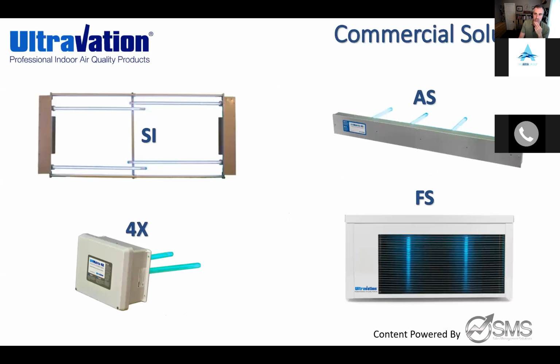But obviously we're focusing on UV. Commercially, we do everything from racked coil lamps to airstream supply, daisy chain bulbs, because that's how you increase your disinfection rates, with those quantities of bulbs through the duct supply. We make this NEMA 4X rated enclosure. This is big for down the shore because it's a waterproof enclosure where all the electronics are inside, kept outside of the equipment, outside the airstream. We can get these with up to 30-inch bulbs mounted on them. These are big if you can't fit a rack of bulbs in there.